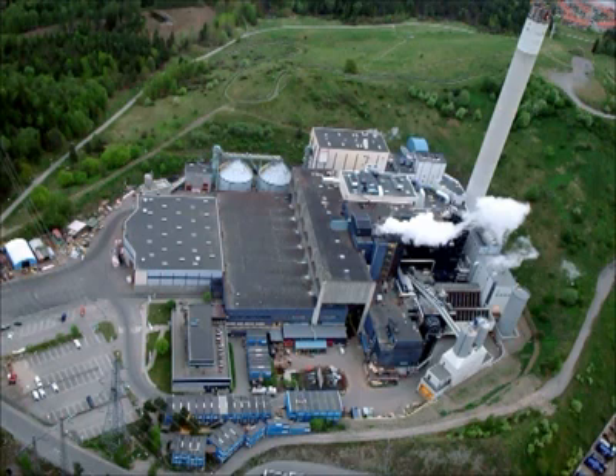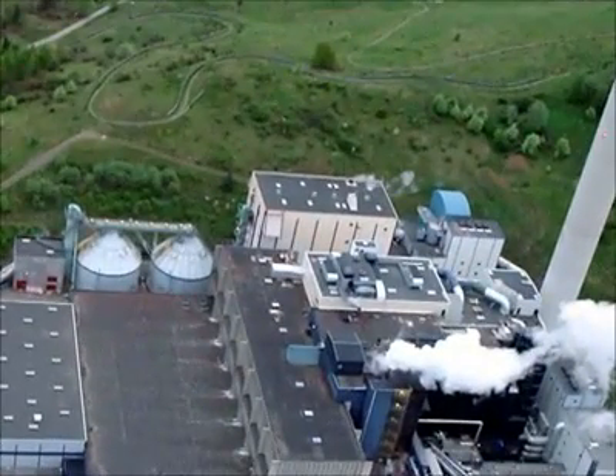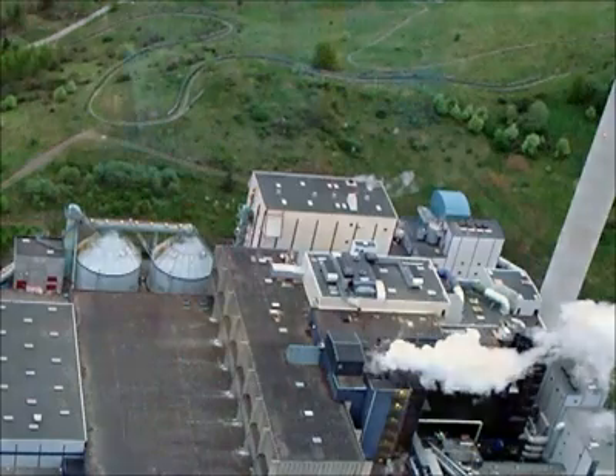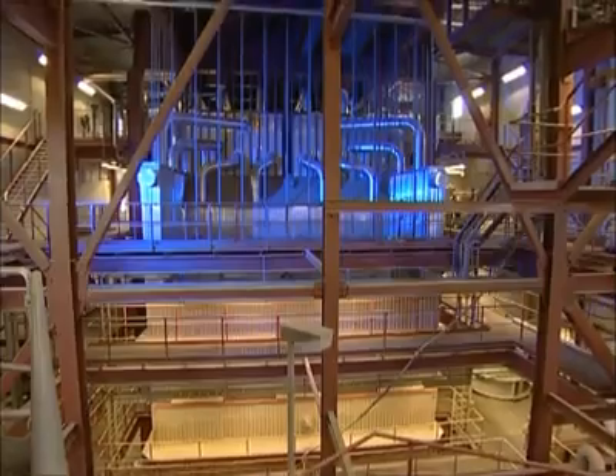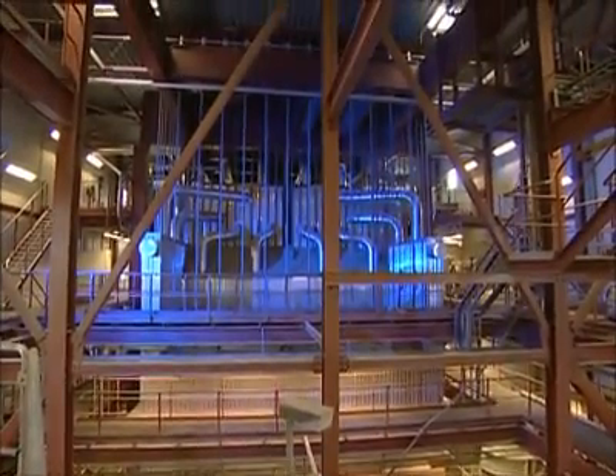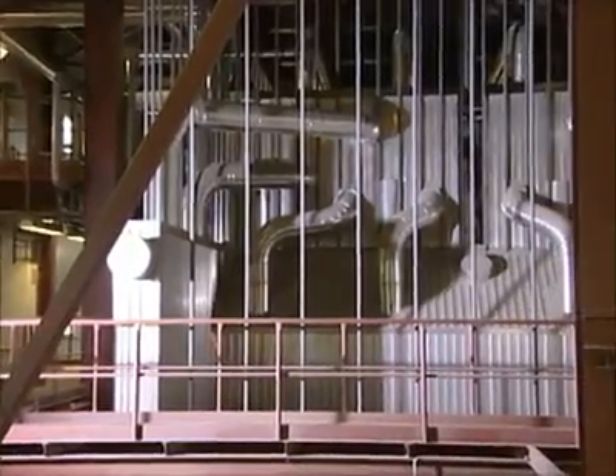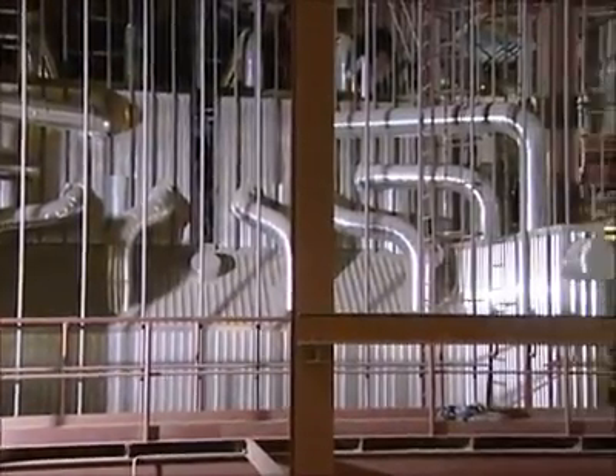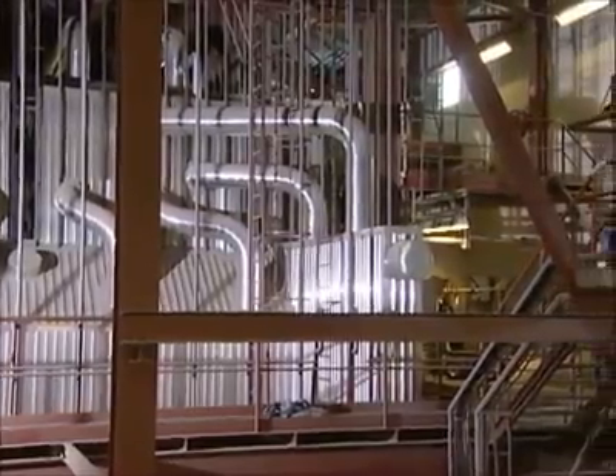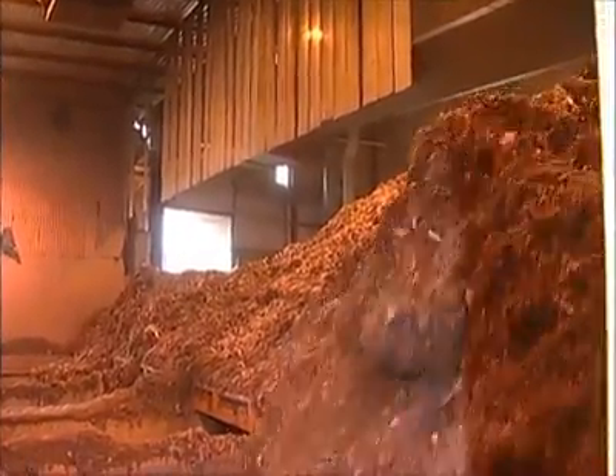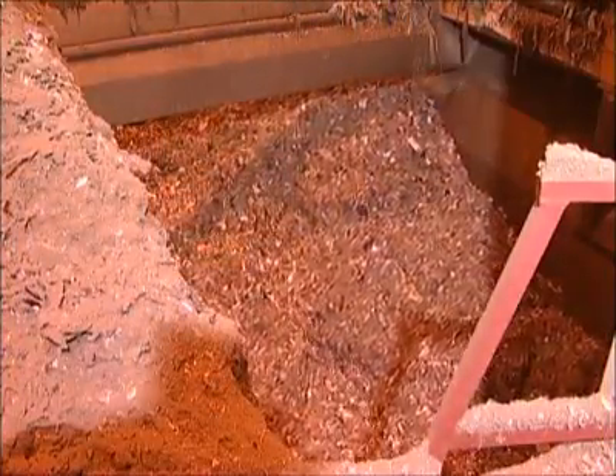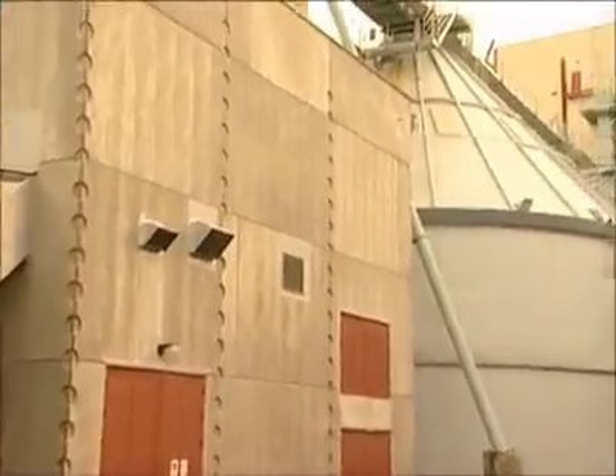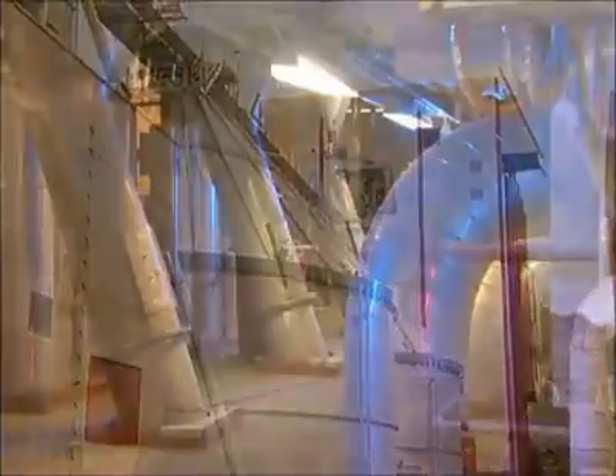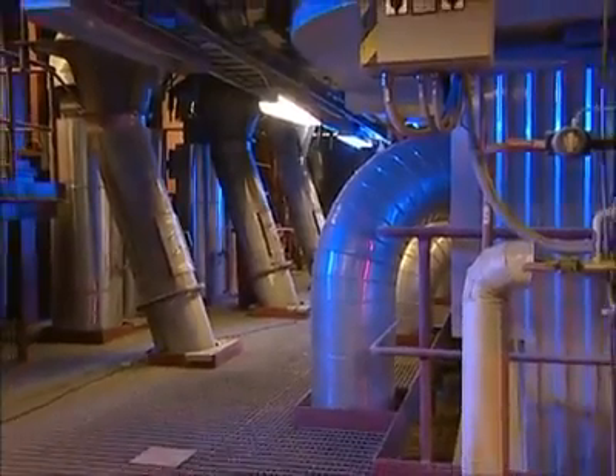The Högdalen heat and power plant has a total of 6 boilers. 4 are fired using household waste, 1 by bio-oil, and then the 6th boiler, which is fired by industrial waste and has its very own production line. Boiler 6 has an output of 92 megawatts. As already mentioned, the boiler is fired by industrial waste consisting of sorted and crushed fractions of paper, wood and plastic. The fuel is emptied into its own stoker hopper for transport onto 2 large storage silos, where it is then automatically conveyed into the boiler via 3 independent fuel lines.